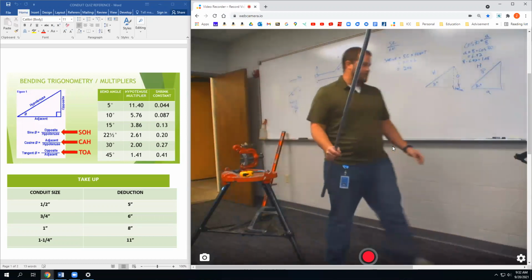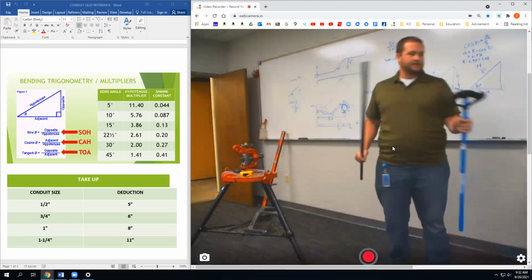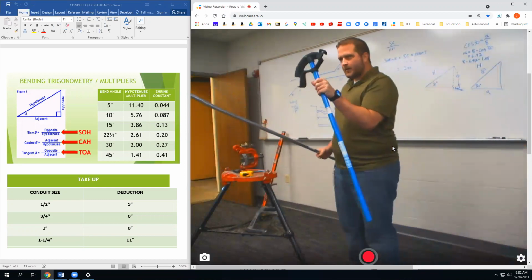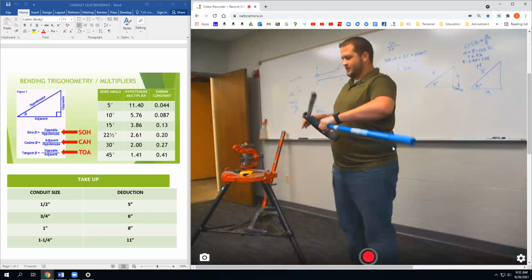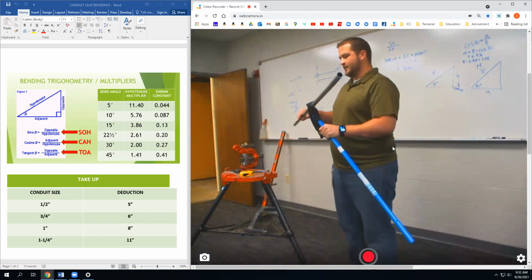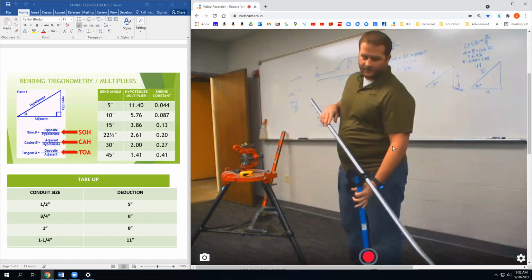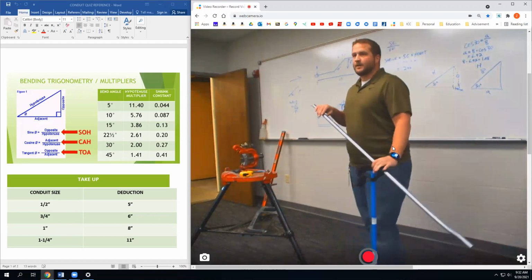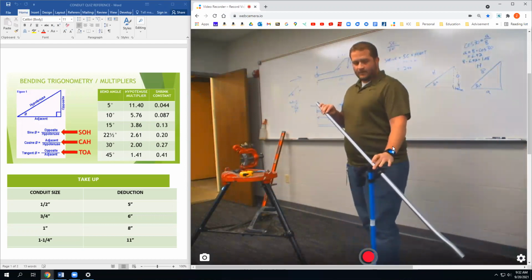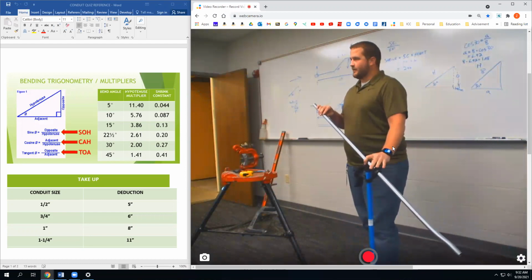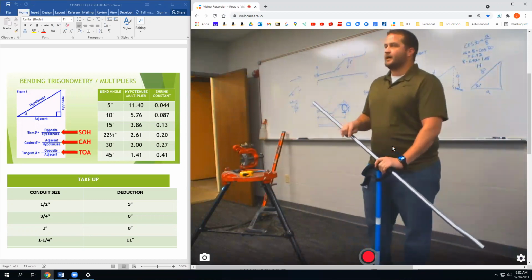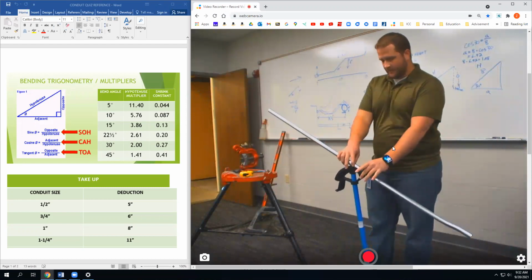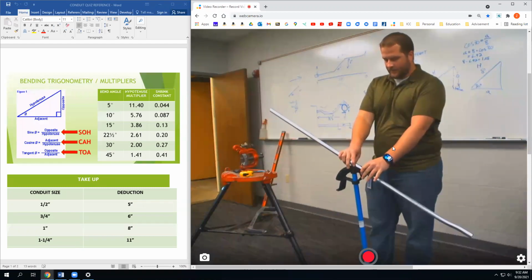All right, which mark on the bender? Notch out. Rim notch. You remember me saying a couple minutes ago, oh, I should have done that on a 45. Remember saying that? Yeah, you said what? Because the rim notch on these benders is for a 45. They don't have a 30 degree. So I'm going to have to, in my head, think about, all right, if that's the center of a 45 degree bend, I need to fudge this a certain way.